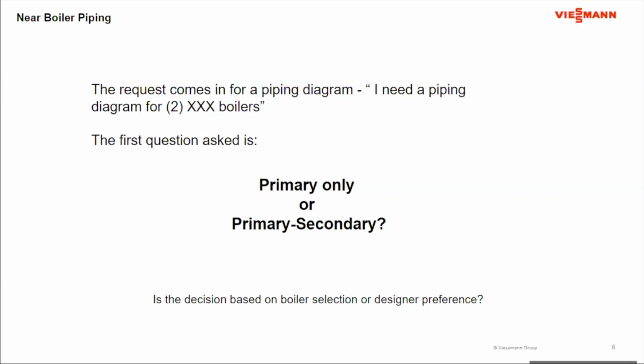So we're really going to look at this, because a lot of times the question that comes up is, when we look at doing this, is the decision for primary-secondary based on the boiler, or is it based on the designer's preferences? That's kind of where we'll start our discussion. And what you'll find from an aspect of near-boiler piping is it's a little bit of both. Sometimes, depending on the equipment, it is based on the boiler design, but sometimes it's really going to be based on preferences. So when we start this conversation, let's talk about a couple of boilers.